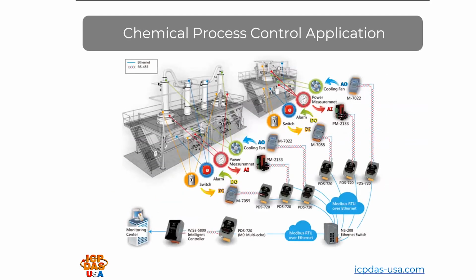Modbus RTU data acquisition devices are connected in daisy chain fashion, similar to connecting daisy flowers together by twisting their stems together. You can see the twisted insulated copper wires in this picture between the PDS720 serial device servers and the M7000 modules and the power meter data acquisition equipment. This picture illustrates the acquiring of analog input information like power, the status of a physical switch being switched on or off. You can see M7055, that's used to turn on digital outputs that trigger alarms based on conditions.